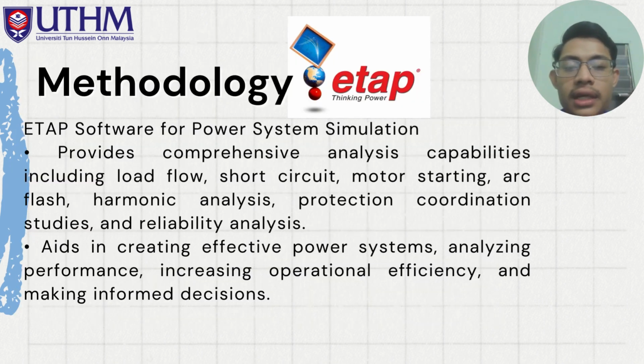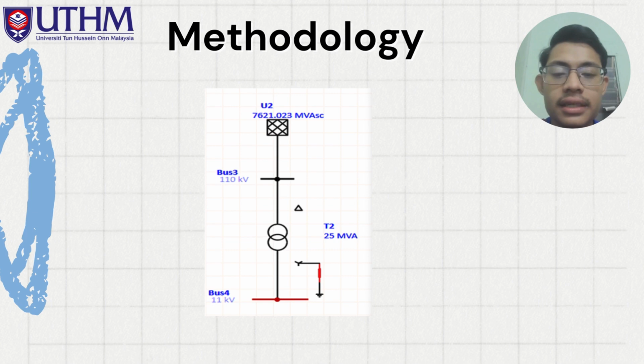The software we are using for the project is ETAP, because ETAP can provide comprehensive analysis capabilities, including load flow analysis, short circuit analysis, motor starting analysis, arc flash analysis, harmonic analysis, protection coordination studies, and reliability analysis. It can aid in creating an effective power system, analyzing performance, increasing operational efficiency, and making informed decisions. In this slide is the small network model for the project.